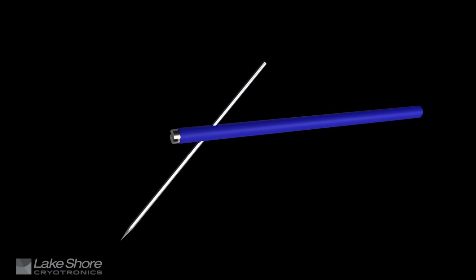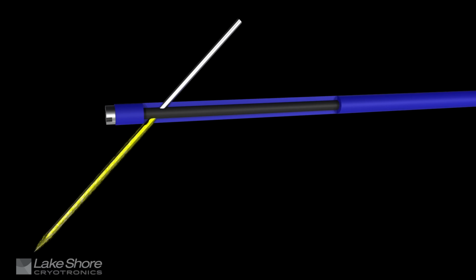A typical DC probe has a needle-style tip that is landed on the sample, where the signal transfers directly to the probe tip via the center conductor of a coaxial cable, with no mechanism for blocking heat flowing with the electrical signal to the sample.